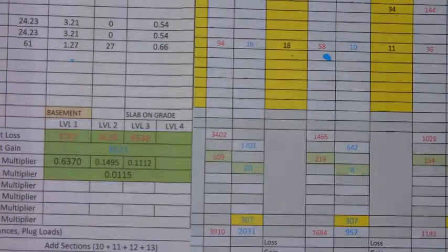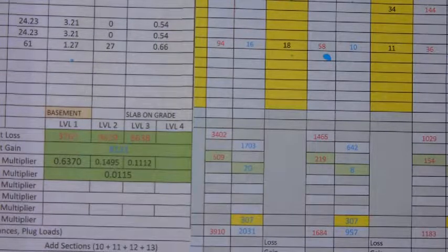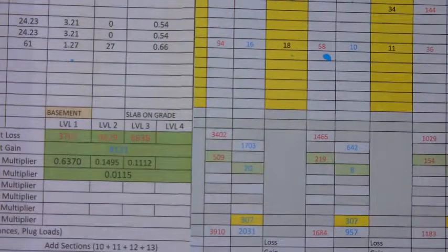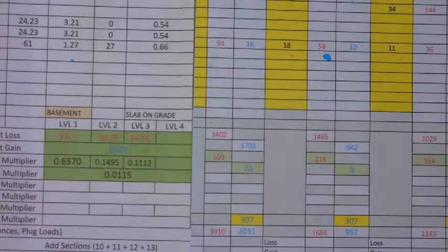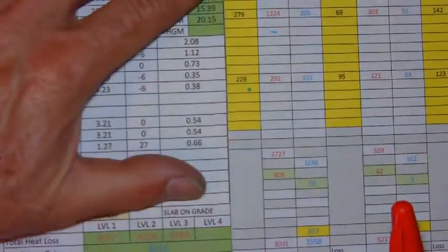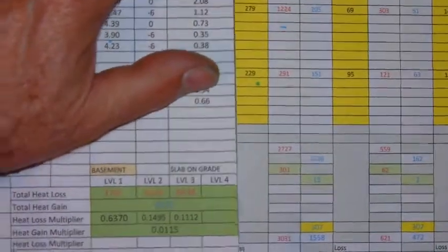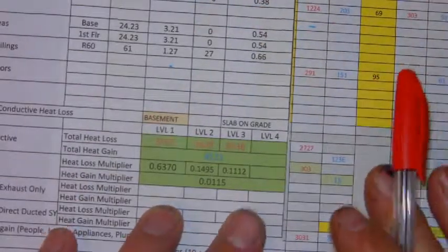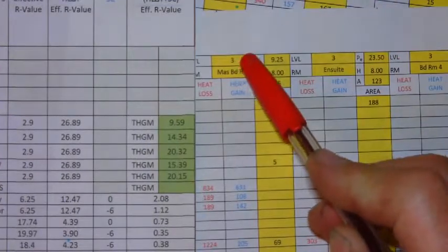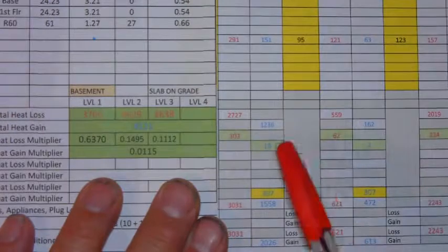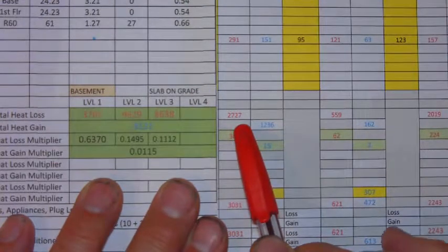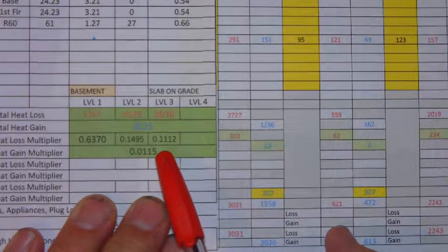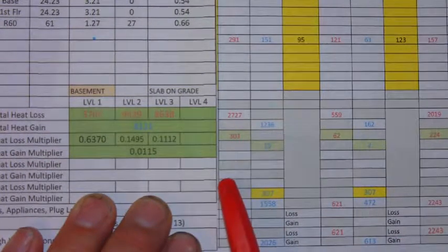Now, if you look at your third floor rooms, then we can see here, here's the master bedroom. The master bedroom is on level three. So you have to use the level three multiplier. So, in this case, you've got 2727 times 0.1112 to give you a heat loss of 303.